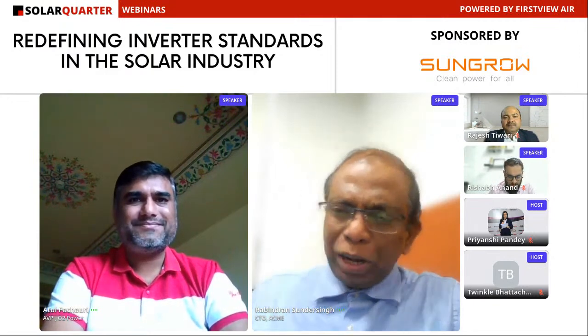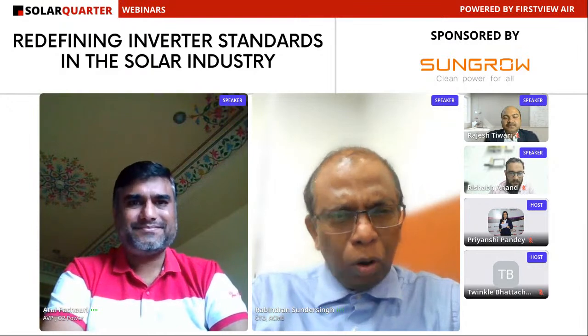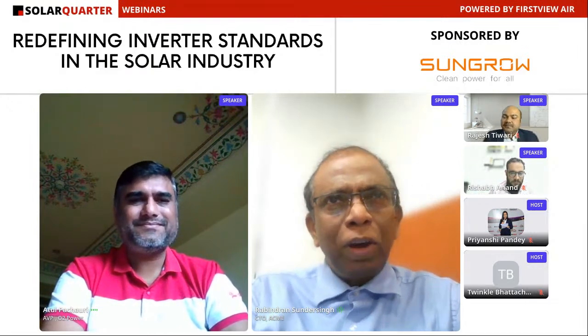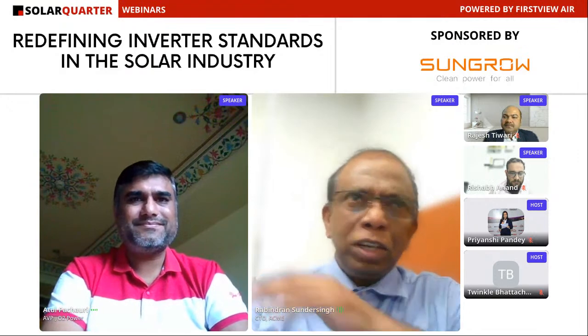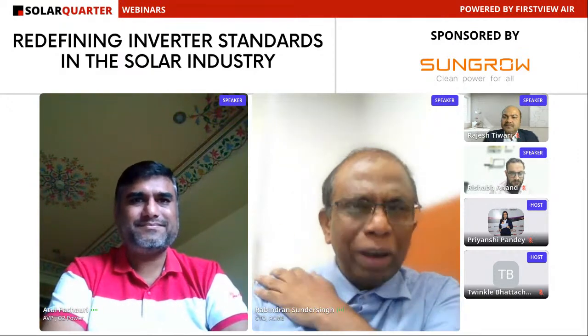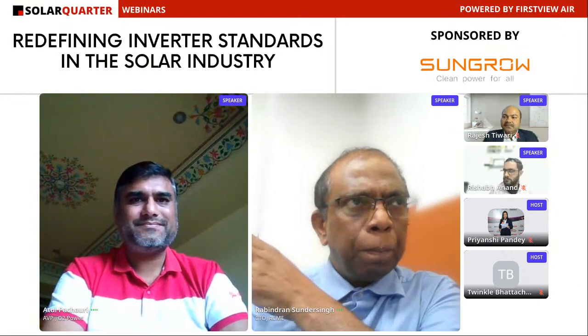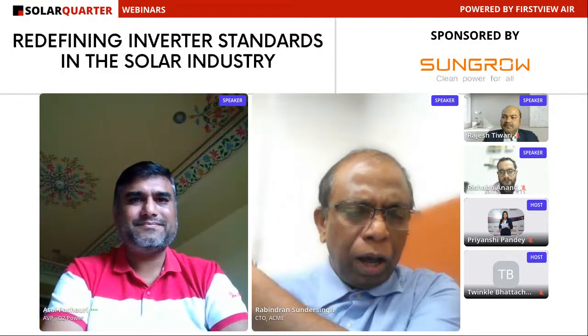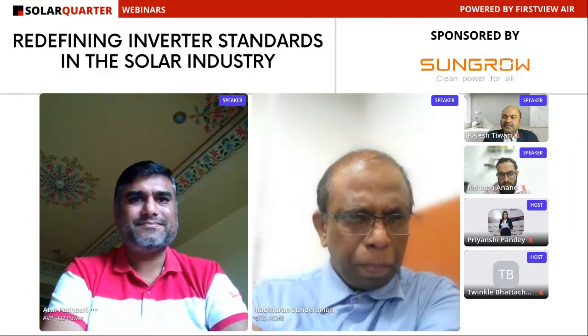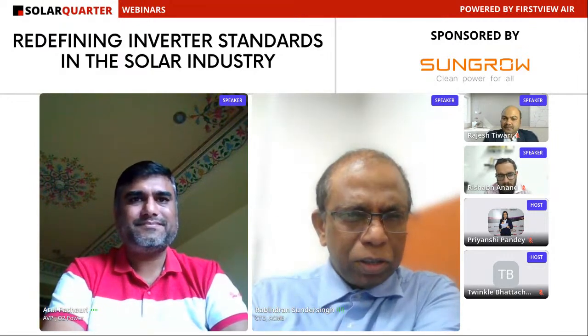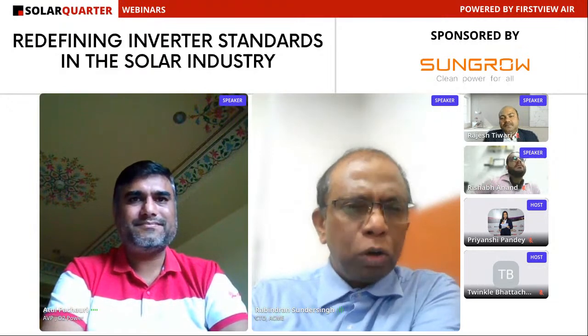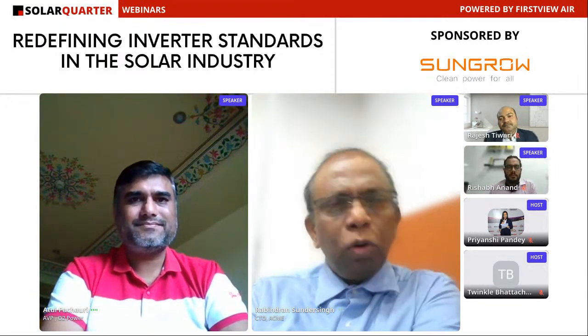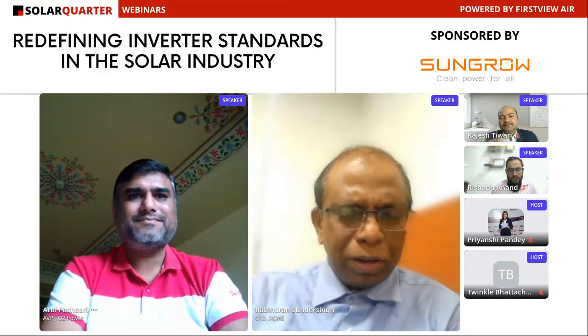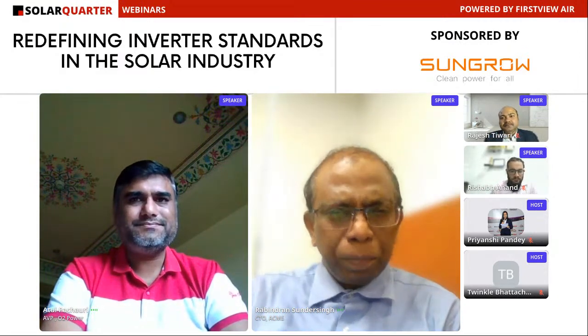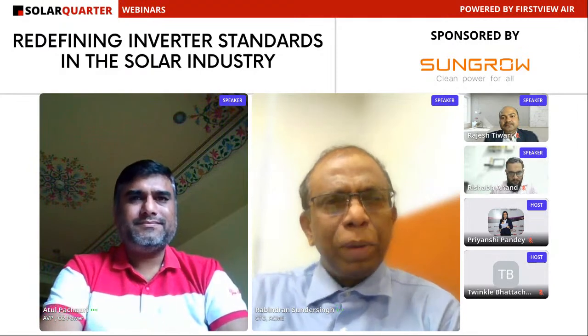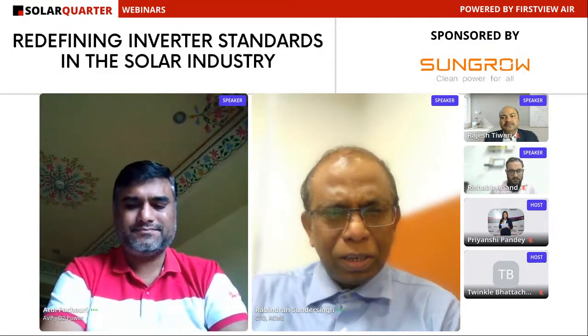Some other things about multiple MPPT mismatch are known facts, especially if I'm doing bifacial. If I'm doing bifacial on fixed tilt with two rows, the way they are arranged, the upper row gets more radiation from the rear, so there's straightaway a mismatch between the two rows. The string inverter can handle such things better. There are central inverters coming up with multiple MPPTs, but that's not the same thing.